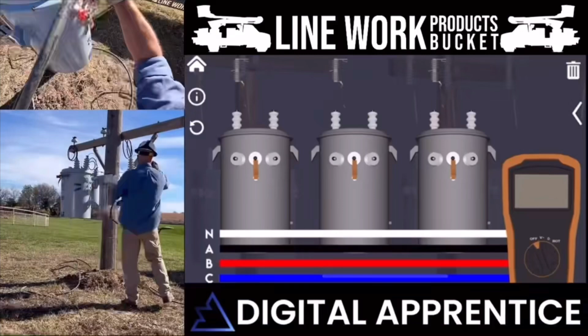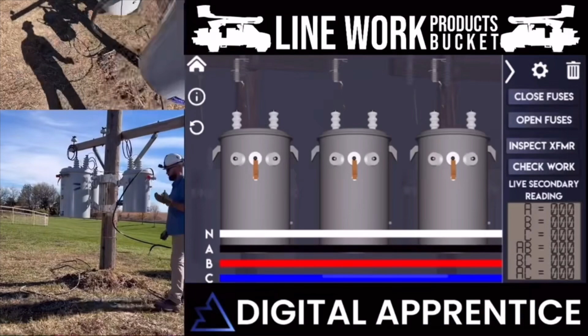So here we have a digital form of this transformer bank you can do on your phone. It's called Digital Apprentice app. The first thing we're going to do is check the parallel of these transformers, look inside the transformers, make sure that they are in parallel. There will be an A, B, C, and D reference on the rods coming out of the windings. Make sure it's AC to X2 and BD to X3. Your X2 will be your neutral.